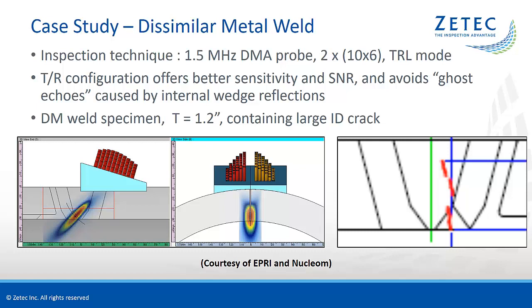In our case study, we used a dissimilar metal weld practice specimen made available by the EPRI NDE Center in Charlotte. The specimen has a wall thickness of 1.2 inches and contains a large branched ID surface-breaking crack. For this purpose, we used a recently designed large aperture DMA probe at 1.5 MHz, where both transmitter and receiver arrays have a 10 by 6 element configuration, and this probe assembly can be driven by the Topaz64 system.